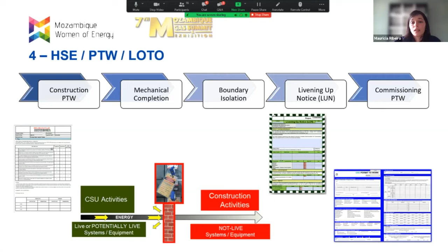After installing our boundary isolations, we do a proper walk down of the system with the HSE. We issue what we call a Livening Up Notice, meaning that from the signature of the commissioning manager on this form, we are now allowed to issue a commissioning permit, therefore starting our commissioning activities.